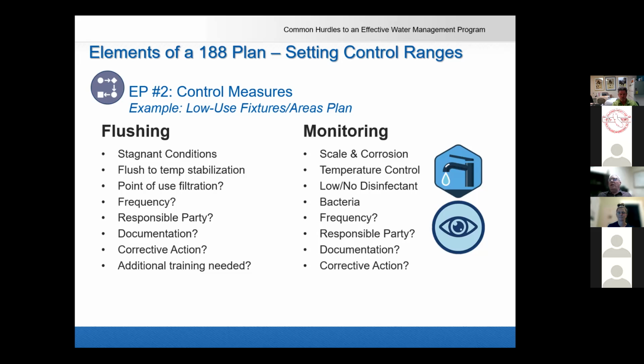And then getting to that sweet spot where I've got 1 part per million chlorine coming in from the municipality, but I notice in the EVS closet, we have very low chlorine and we flush it on Thursday night. We come in, we measure it on Saturday and we see that it's now up to about 0.8. Are we flushing too long? Are we flushing not long enough? So this can be a process that's ongoing.